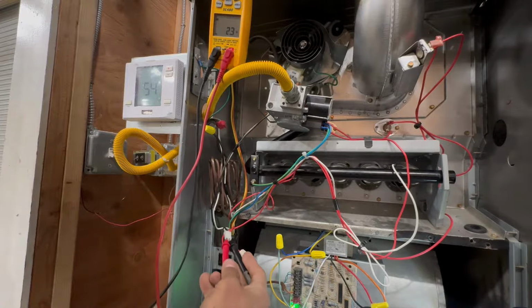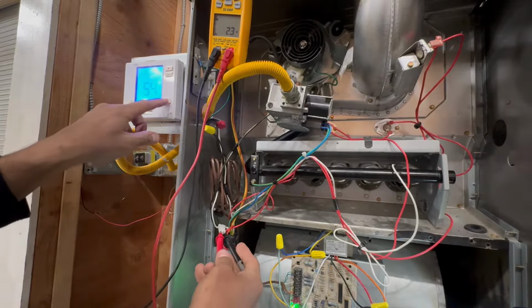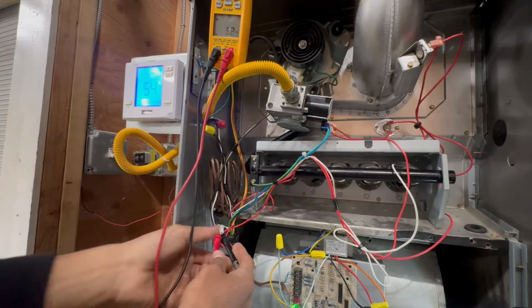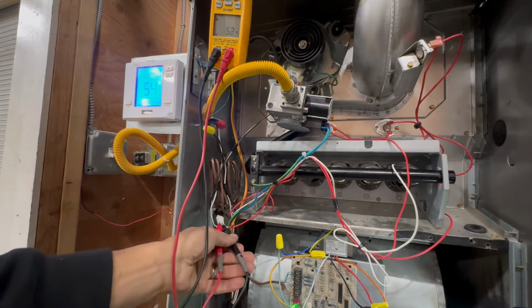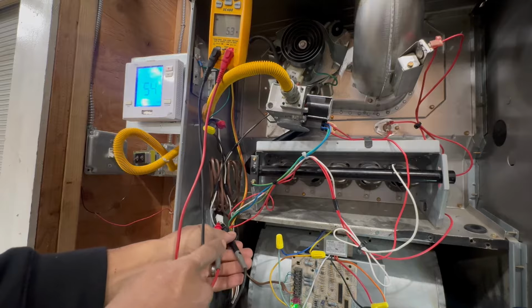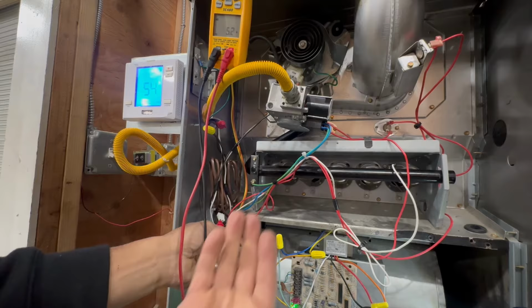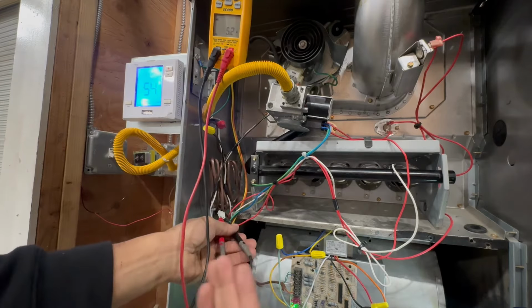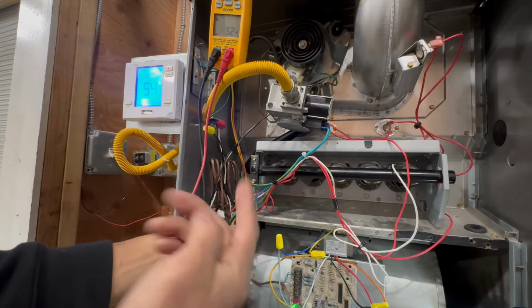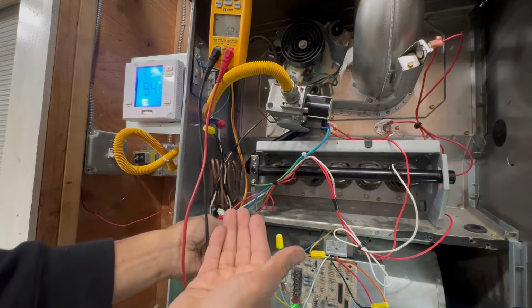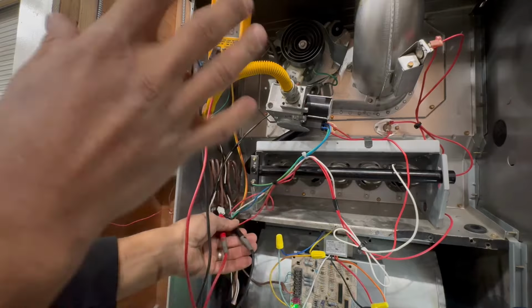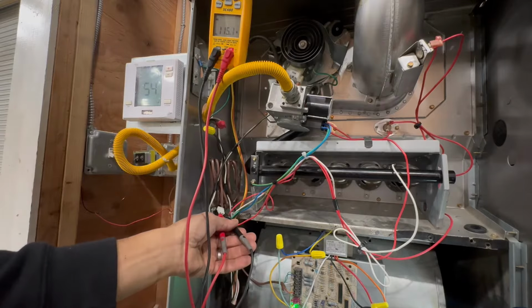Okay, so we're good. So let's go ahead and call for heating. All right. Look at my meter, right? It's gonna send 120 volts. Obviously, I disconnected that hot surface igniter, but I just want you to see that this is how you would check if the board is actually sending 120 volts, right? If it's doing all its steps, but it doesn't send 120 volts, there's a problem.